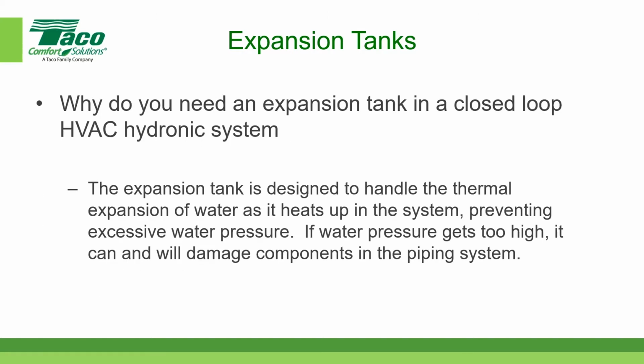One of the first things I want to mention, and probably 99% of you already understand, is why an expansion tank is required in a closed loop hydronic heating system. The bottom line is the water, or mostly-water mixture with maybe some glycol, expands as it heats up. If there's no place for that to go, it increases the pressure in the system and tries to find a way out. If it gets too high, something bad is going to happen, a component pops, a relief valve goes, something bad happens. That's why expansion tanks are important and necessary.